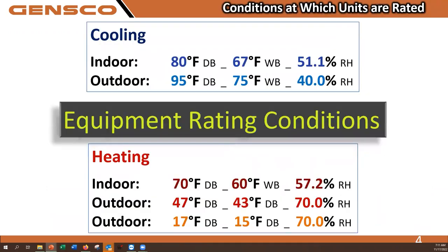Now, when you're talking about how equipment is rated, where did that rating come from? A lot of people aren't aware that in cooling, that output rating was done at an 80-degree return air. And it's very rare that your customers are going to have a set point of 80 degrees. If you actually reduce the temperature in the space to their normal set point, say 73 maybe, the output that is listed as the cooling rating will actually be less than what it's rated, because at 72, I have less heat to work with. Outdoors, it's 95-degree air.